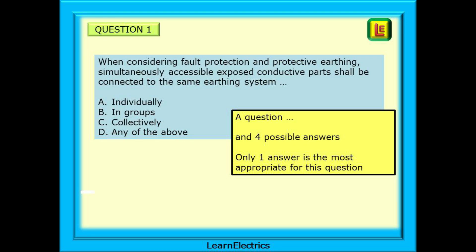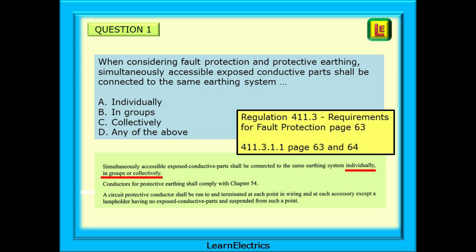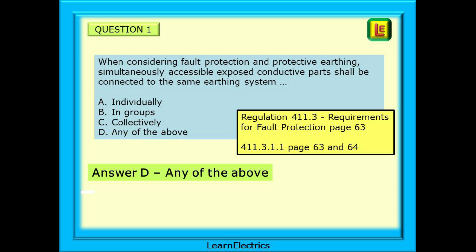The question asks: when considering fault protection and protective earthing, simultaneously accessible exposed conductive parts shall be connected to the same earthing system — and then four possible answers complete the sentence. Only one answer is most appropriate. Regulation 411.3 on page 63 is about fault protection. Regulation 411.3.1.1, as shown below and underlined, gives us the answer. We should choose answer D — the regulations say that we can use any of the listed connection types.